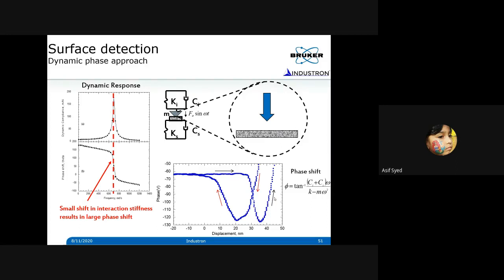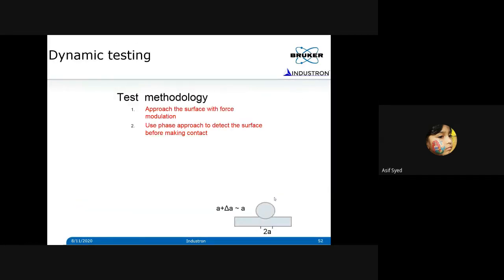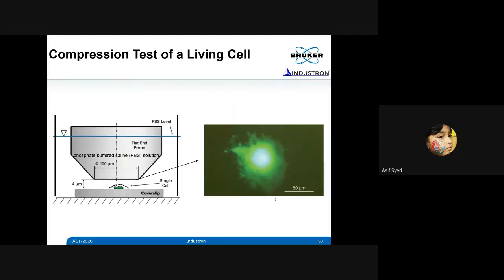So measuring the phase shift is a very sensitive way of sensing the surface, and using that, you can do a lot of good things. One thing that I would like to show you is how you can do a compression test of a living cell, okay? Using a fluorescence microscope, which comes with the instrument when you buy the fluorescence microscope option, you can put a biomarker, you can see the cell, and if you use a very flat-ended tip, in this case about 100 micron, you can bring the tip into alignment with the cell that you want to test, and then make contact, okay?